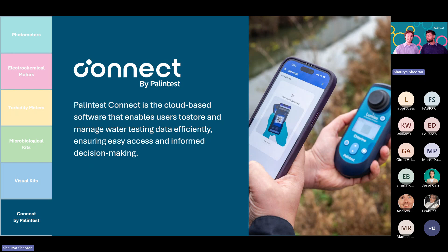So now we're going to explore why you actually want to test for monochloramine and ammonia. To start, what is monochloramine? It's a disinfectant used in large building applications and in areas where housing and businesses are sparsely populated, basically anywhere with really long pipe networks. Monochloramine is formed by combining ammonia and chlorine, and to do this right you have to strike a very specific ratio between those two compounds.